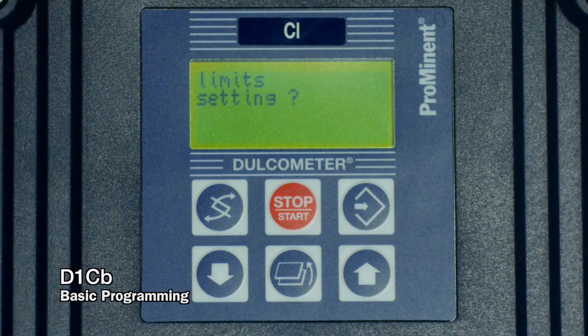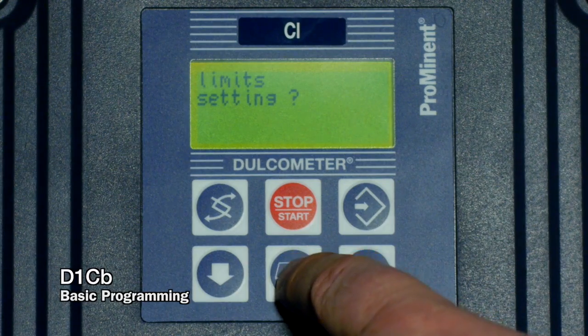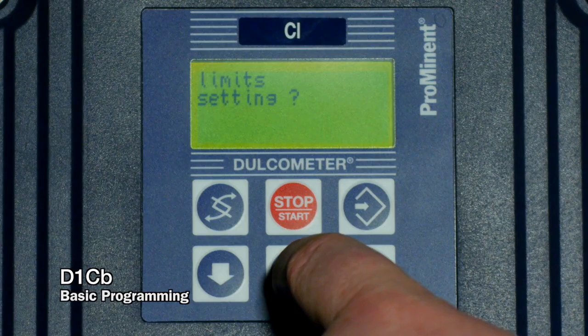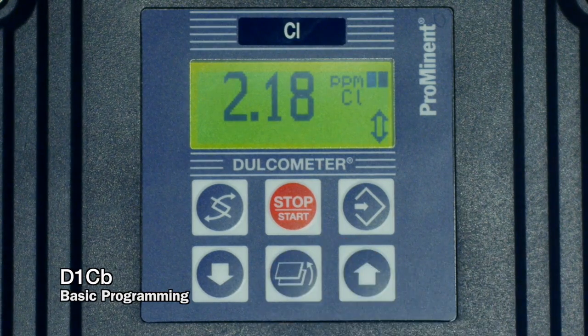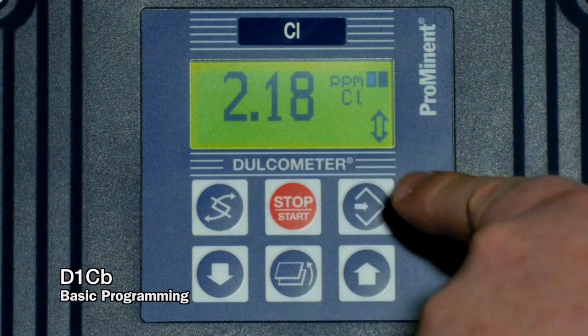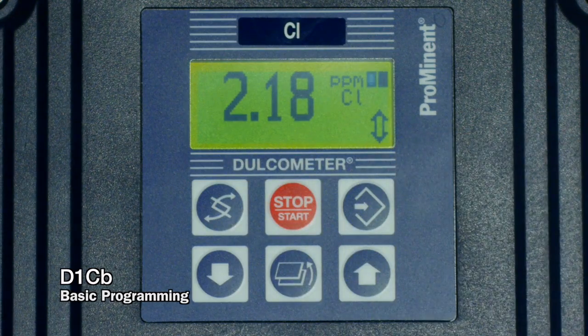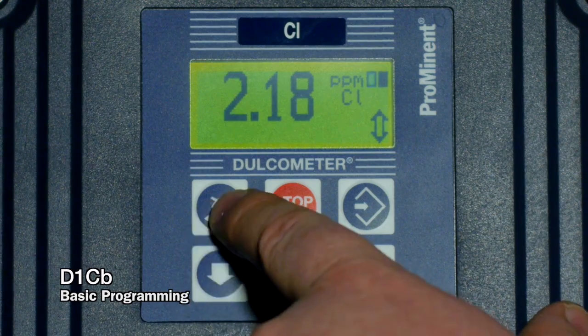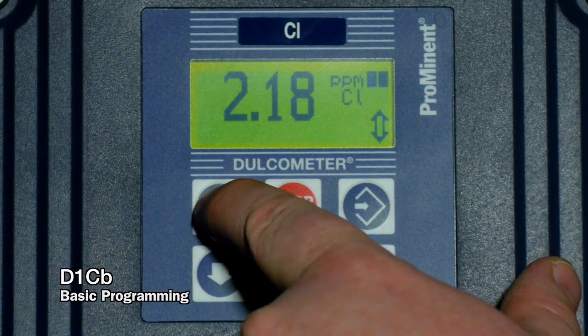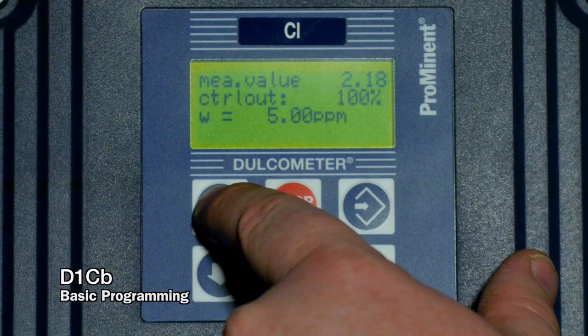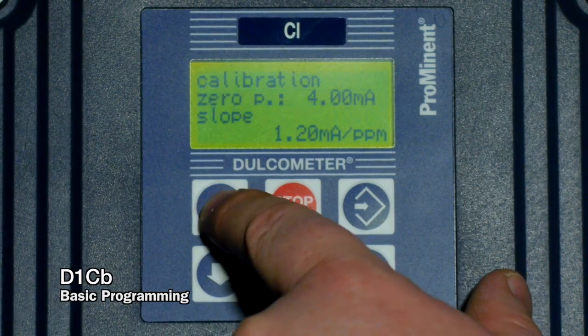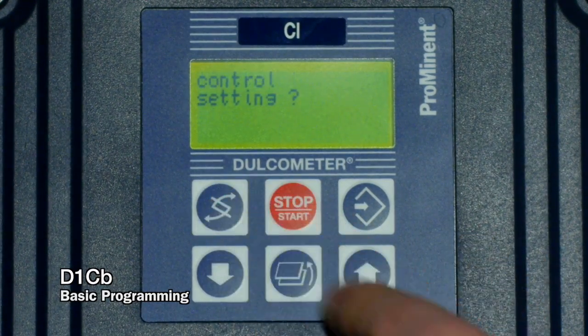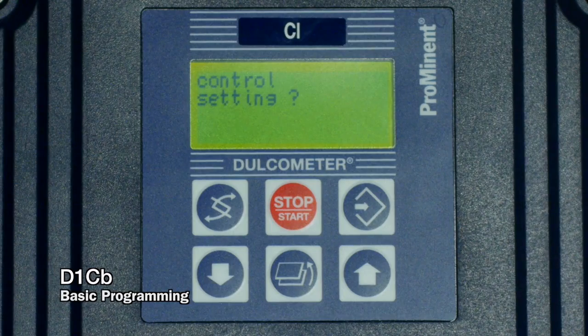Hit the enter button again. You'll see it moves on to the next menu. We don't need to pursue that any further. We can hit the bottom center key, get back to the main display. You'll see that calibration at the bottom has gone away, and our error at the bottom has gone away as well. The next thing we need to do as simple startup or simple setup on a D1CB would be our set point.